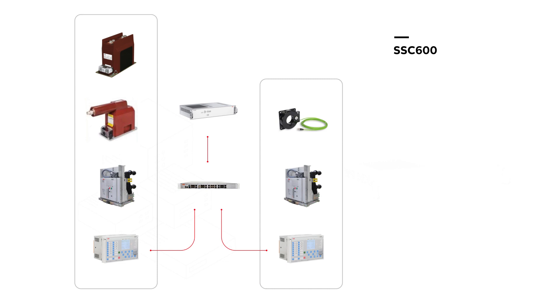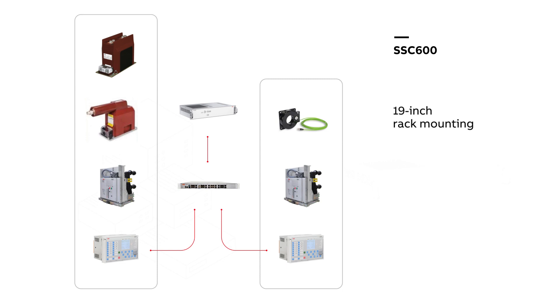We have a similar setup as we saw earlier, but here in this case all the signals from inside the switchgear panel are sent to the protection relay, which serves as the main protection unit. It protects the panel and the switchgear. All the data is sent over the communication network to the SSC 600. The size of the SSC 600 device is a 19-inch rack, which means it can be easily mounted inside the metering panels bus section, so it all stays within one switchgear.